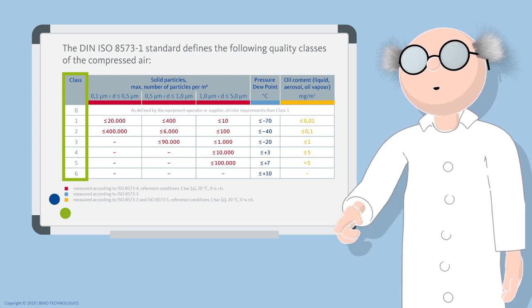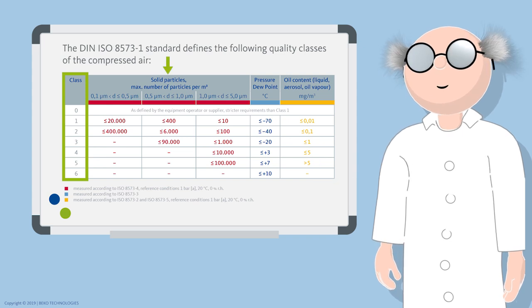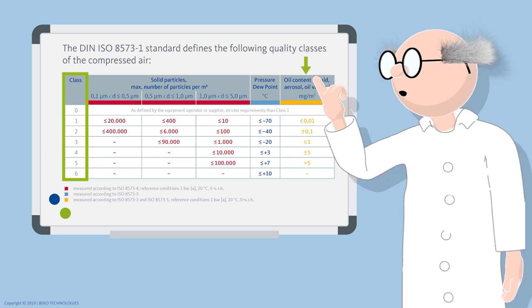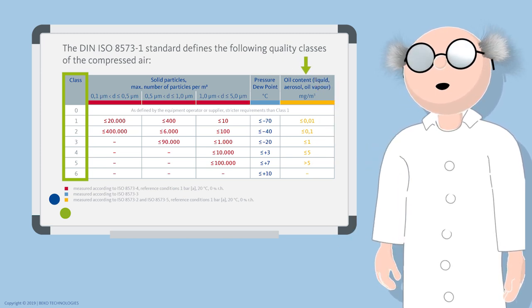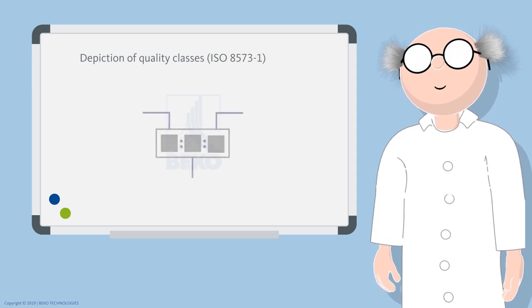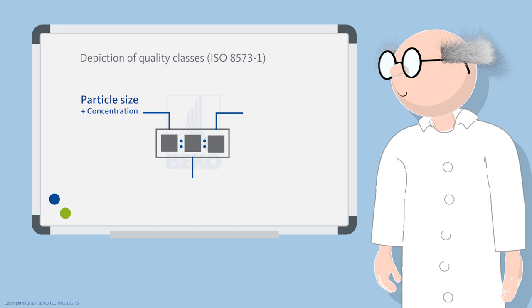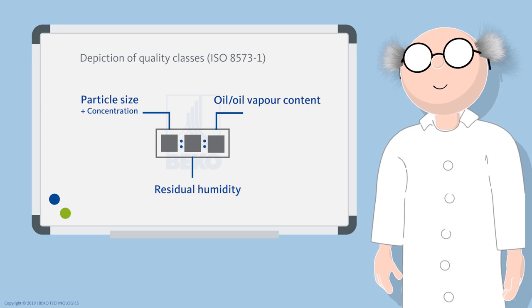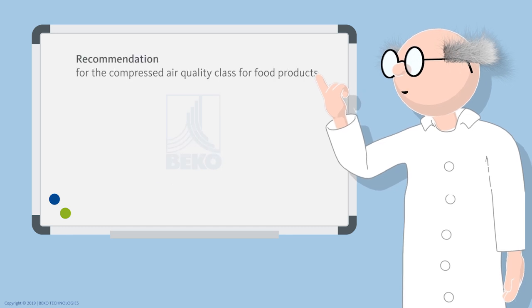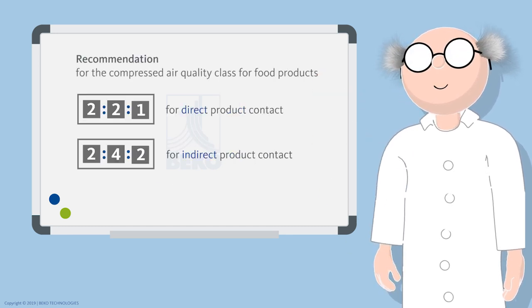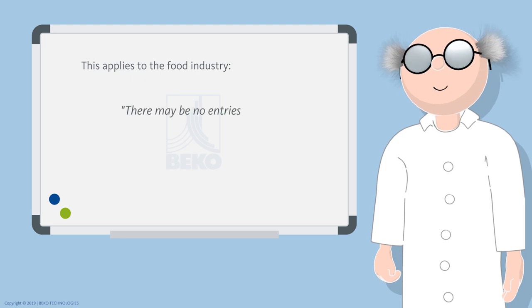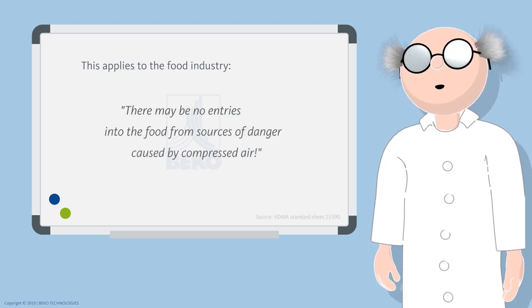The standard ISO 8573 stands for the quality requirements for compressed air and specifies the maximum content of solid particles, air humidity, and residual oil or oil vapor that may be contained in the respective classes. The quality classes for compressed air are indicated by three digits: the first digit stands for the particle size, the second for the residual humidity, and the third for the oil or oil vapor content. Depending on the required quality class, appropriate treatment of the compressed air is necessary — there may be no entries into the food from sources of danger by compressed air.